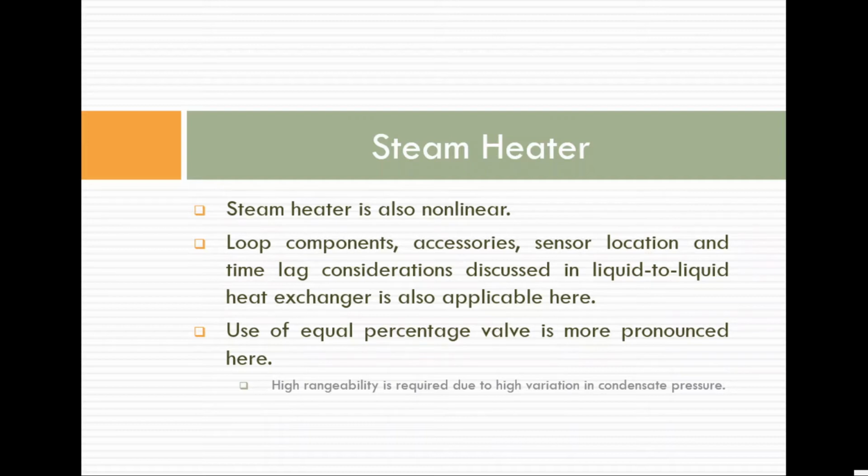Why are we using an equal percentage valve? An equal percentage valve is used to maintain the loop gain constant, and here the steam heater is demanding an equal percentage valve more than the liquid to liquid heat exchanger. To explain that, let us see why we are using a steam heater.